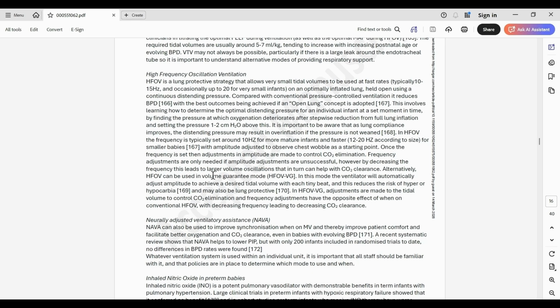Alternatively, high frequency can be used in volume guarantee mode. Okay, so there's a little bit we've got to unpackage in this situation. They talk about this HFOV-VG. This isn't available on ventilators in the United States. My understanding is that the mode is not able to get through the FDA, because with a lot of these ventilator modes, we're not going to be able to declare that a single mode is superior to another one. They can maybe do non-inferiority type studies, but the way these studies are required to be done limits our ability to use these modes in the States. Over in Europe, they can do what they want in terms of this, but that's one of my biggest gripes with the control the government has over what we're able to practice, but we're not going to get into that.